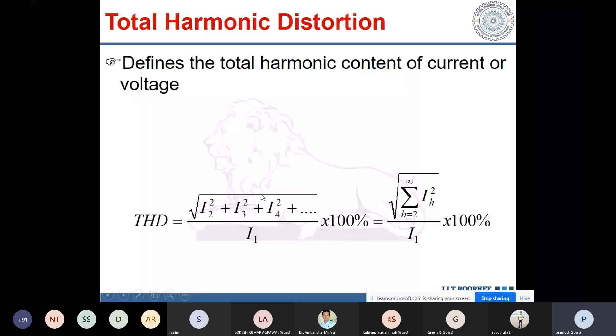And we discussed in the previous class, ideally harmonics should be 0. So one should say THD should be 0. But certain harmonics will be present. You cannot make it exactly 0. And therefore, supply authorities put a limit on how much harmonic you can inject into the system. A typical value is 5%. Although from equipment to equipment, whether it is low power or high power, whether it is on the distribution side, or depending upon whether it is an industrial or a residential one, the THD limit is different, but the typical value is 5%. So if it is within 5%, it is fine.